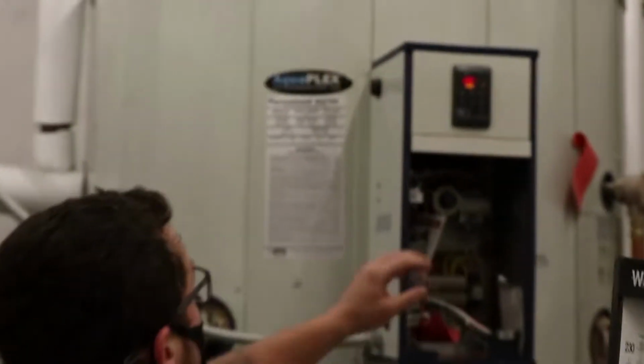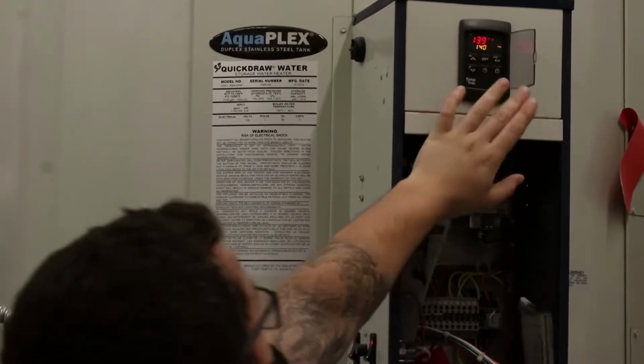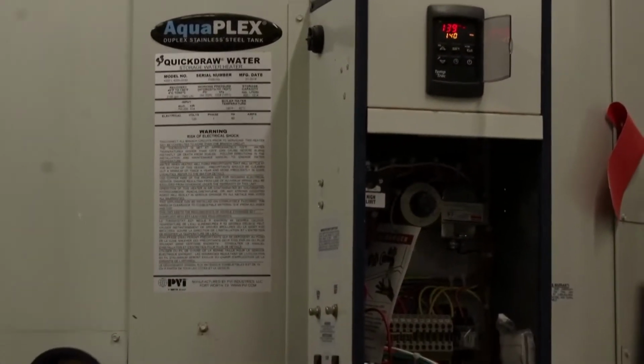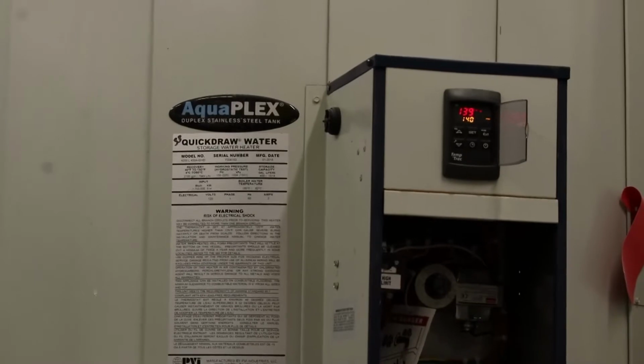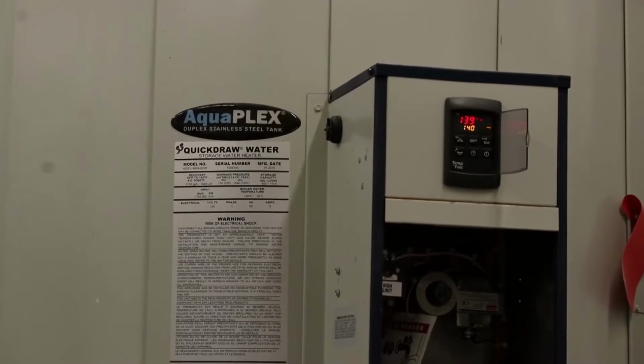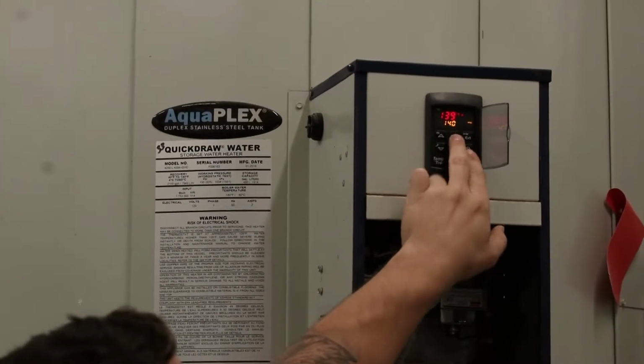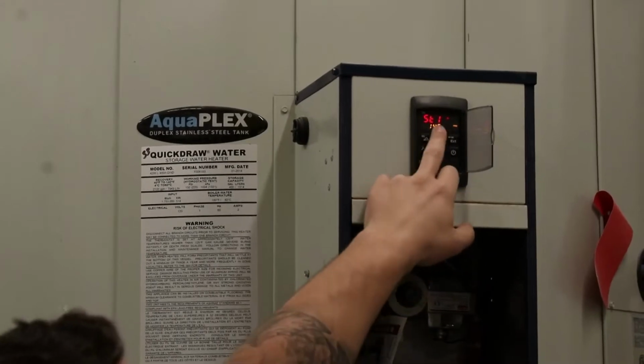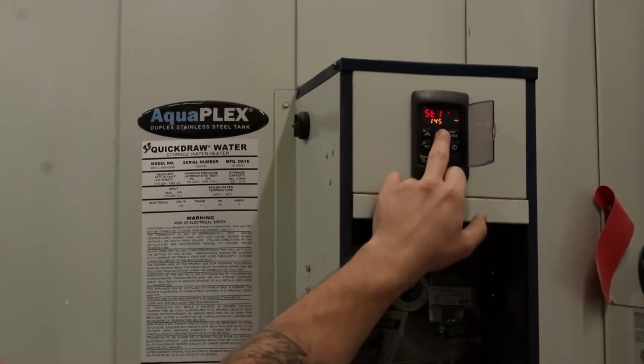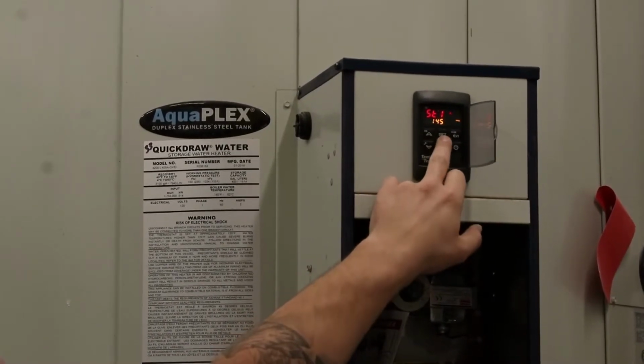The main control, you have your temp track controller. This contains the parameter ST1. ST1 is your primary set point. On these heaters, they are set to 140 degrees. So if you press set, ST1, I'm sorry, they're set to 145 right now. This heater, you have ST1 145.